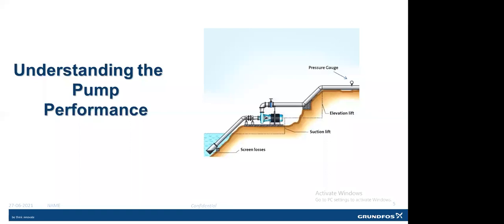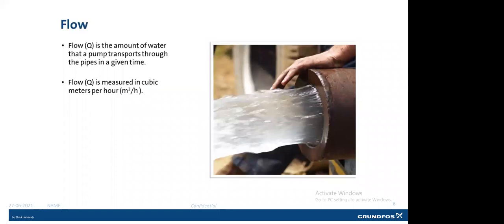Before that, we'll understand the pump performance, how to assess it, and what the terminologies associated with it are. As we are aware, a pump is designed based on flow and head. Flow is nothing but the amount of water transferred in a given period of time, and it can be measured in many units like meter cube per hour, GPM, LPS, or liter per minute, etc. First, we need to check in which unit we need to measure the performance. For calculating the efficiency, if we are taking the flow in GPM, we need to consider head in feet. So first we need to finalize the units.